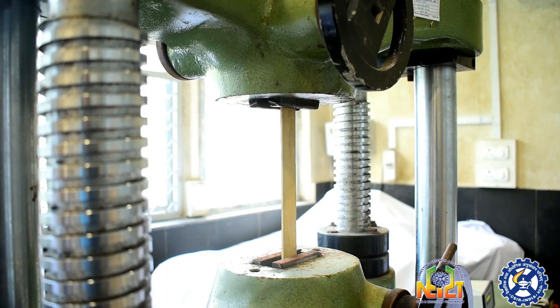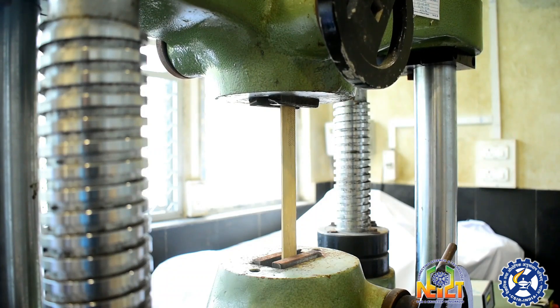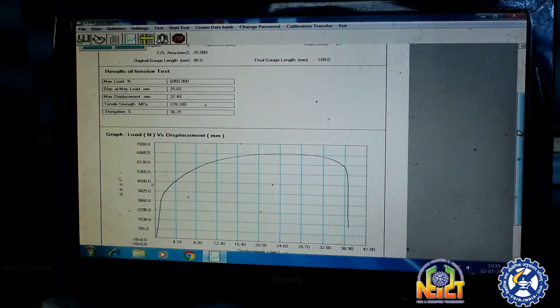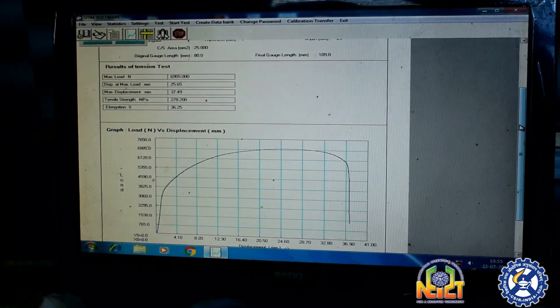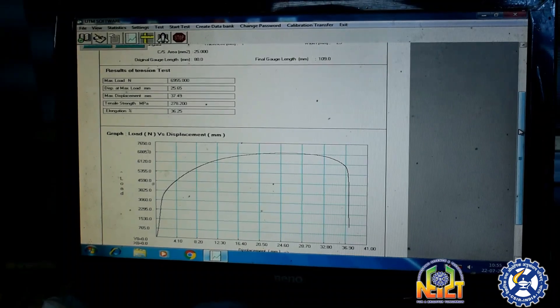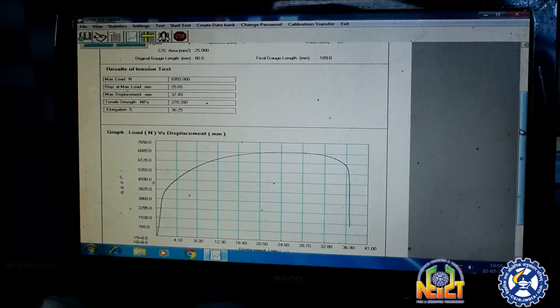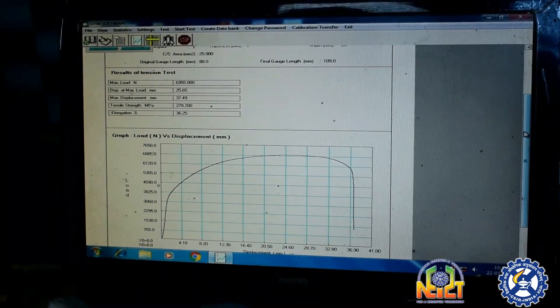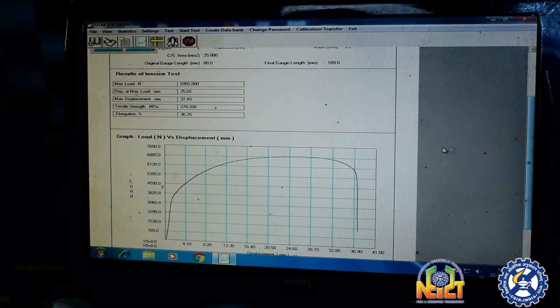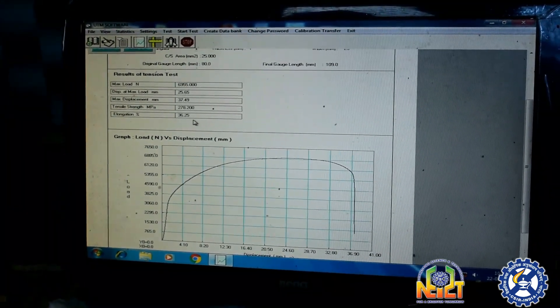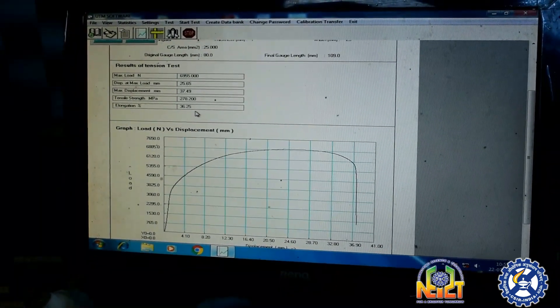Simultaneously run the software. Instrument is running now. The results are appearing in graph form of load versus displacement. The tensile strength value is coming to 278.2 MPa and elongation 36.25%. Thank you very much.